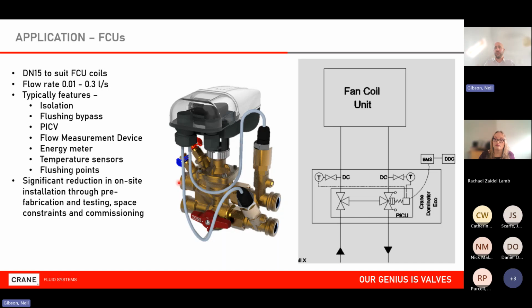So we have a compact valve set. This is known as our Dominator Eco. We've got a PICV built within this section here with an integrated bypass. Some test points here if someone really does want to measure flow rate or pressure. And what we have here, traditionally, we have flushing valves used as part of the commissioning process. We've got an adapter in here, which allows us to put the temperature sensor in. It's a contact temperature sensor.